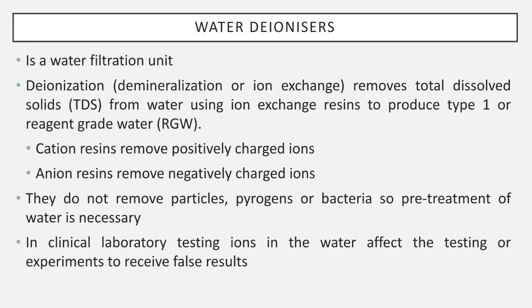So these water deionizers contain different resins, like cation resins which remove the positively charged ions, and anion resins which remove the negatively charged ions. So positive and negative charged ions are removed, but this cannot remove particulate matter and also pyrogens or bacteria.